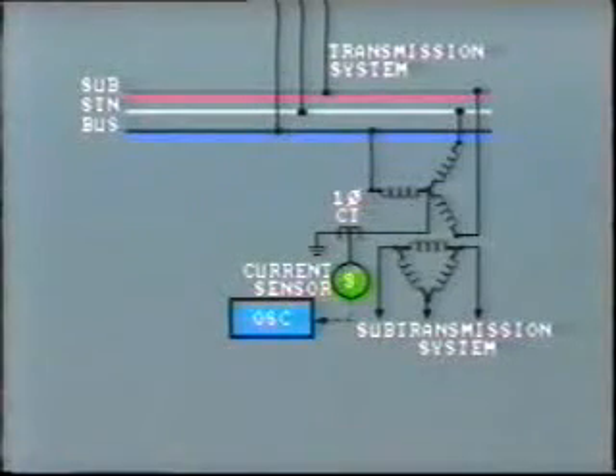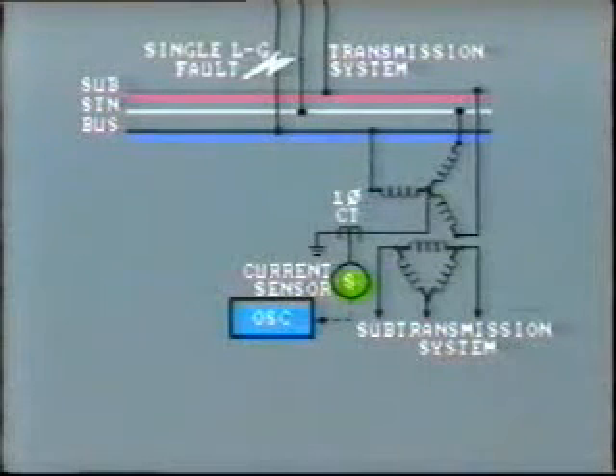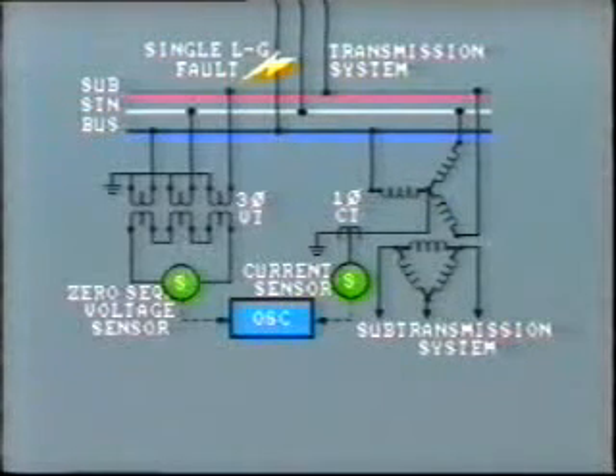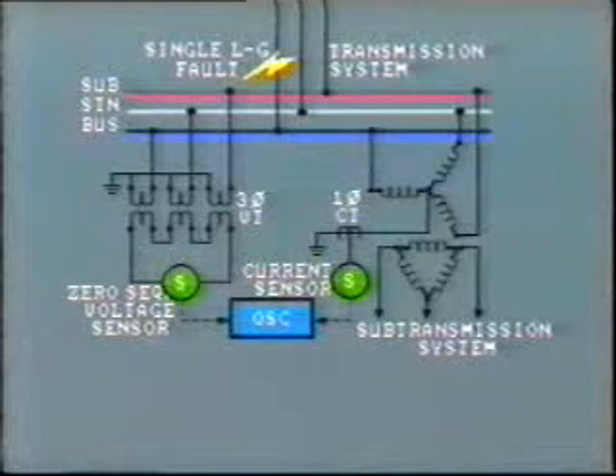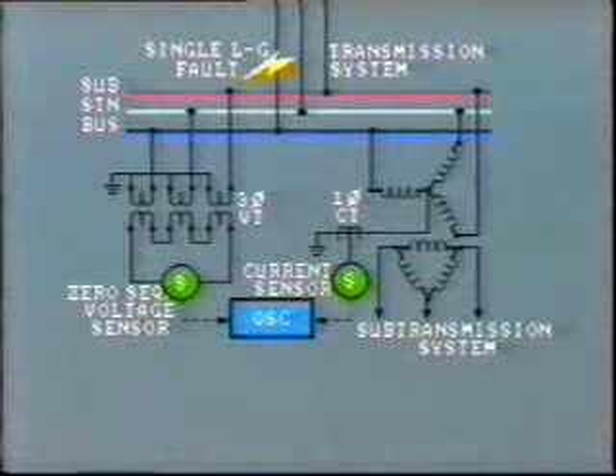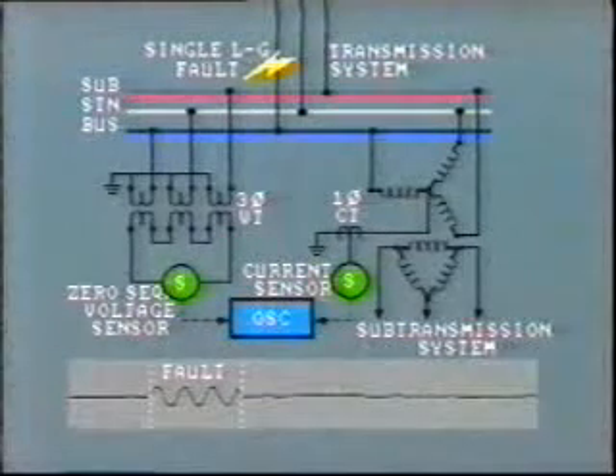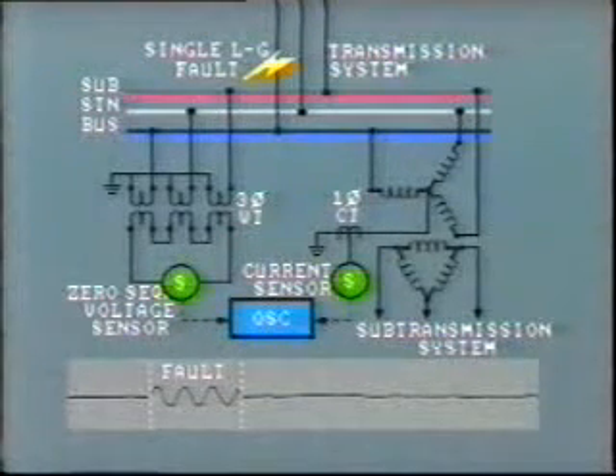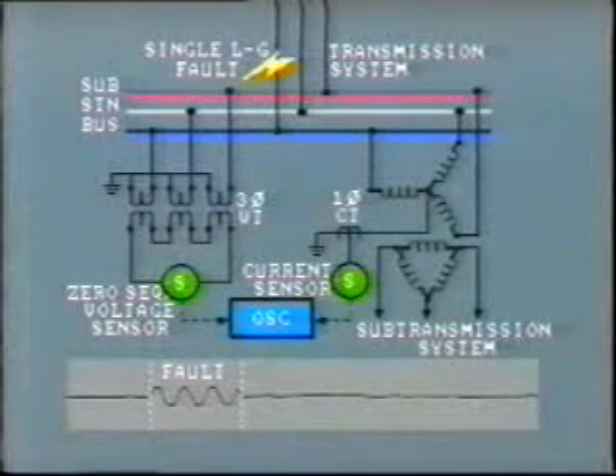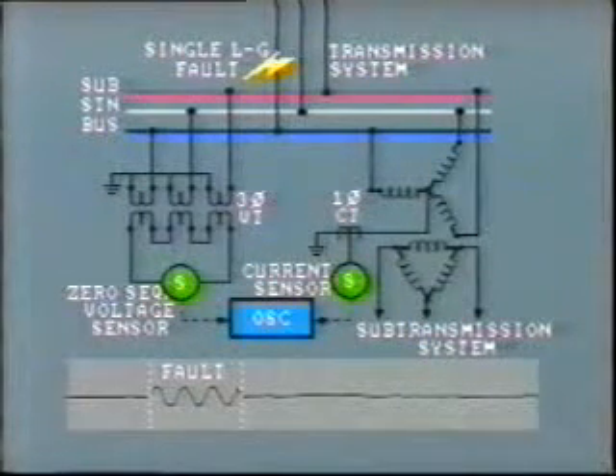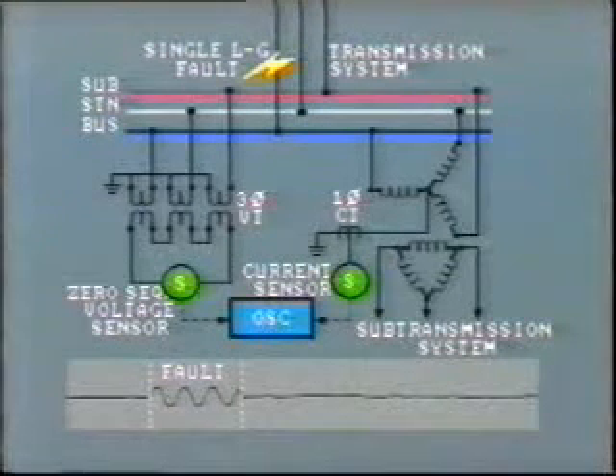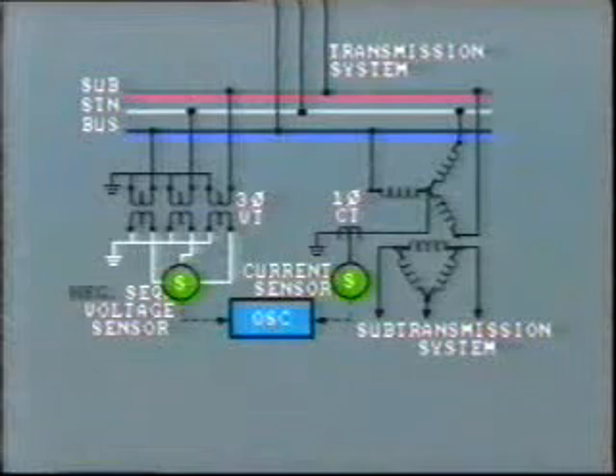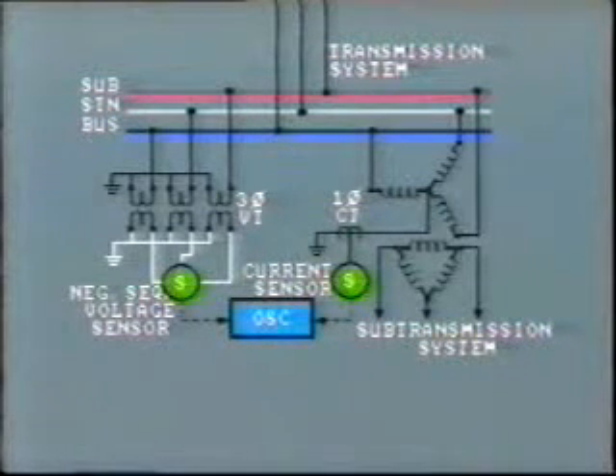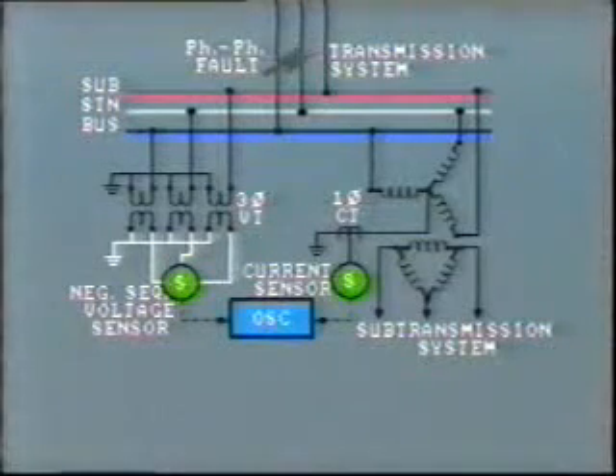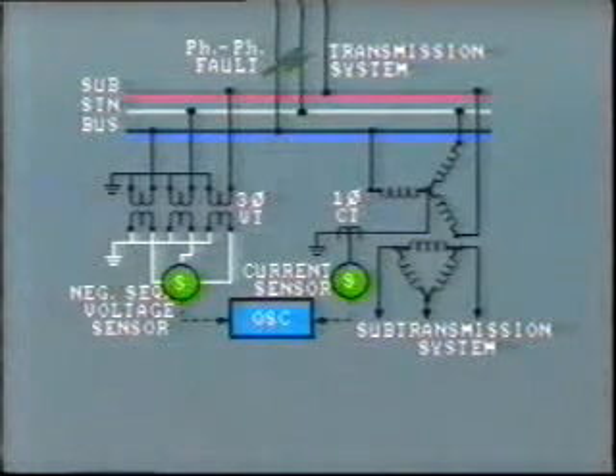For example, this overcurrent sensor in the neutral circuit of a transformer detects single line-to-ground faults out on the system. Often this sensor is backed up by a zero-sequence voltage sensor connected across the broken delta winding of a voltage transformer. This measured voltage is zero under normal conditions, but it greatly increases for a line-to-ground fault. Thus, we can set the voltage sensor very sensitively to provide good backup for the current sensor. We can also use a negative sequence voltage sensor connected to the bus. This will sense a phase-to-phase fault on any line connected to the bus.